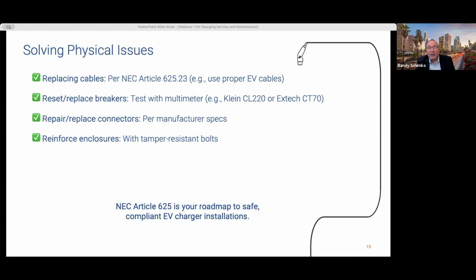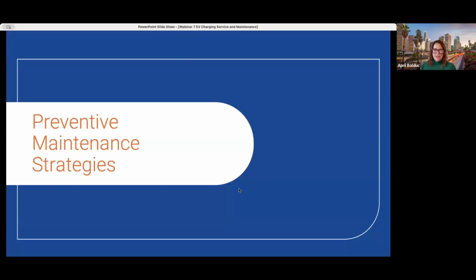For repairing or replacing connectors, stick to the manufacturer specifications. Worn pins or cracked housings need precise fixes or replacements to maintain a solid charger to vehicle connection. To reinforce enclosures, use tamper resistant bolts to protect against vandalism. This strengthens screens and casings, keeping chargers more secure and operational. And remember that NEC Article 625 is your go-to guide. It lays out the rules for safe, compliant EV charger installations and will help to ensure that all repairs meet industry standards. Next, we have preventative maintenance strategies, Randy.